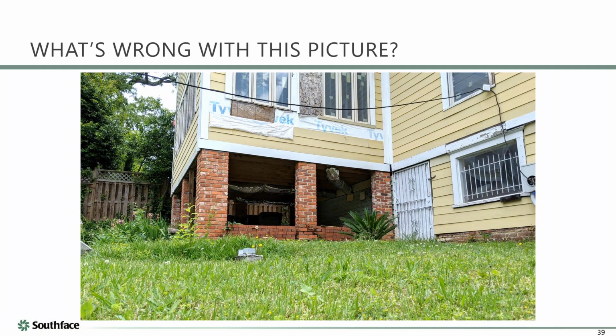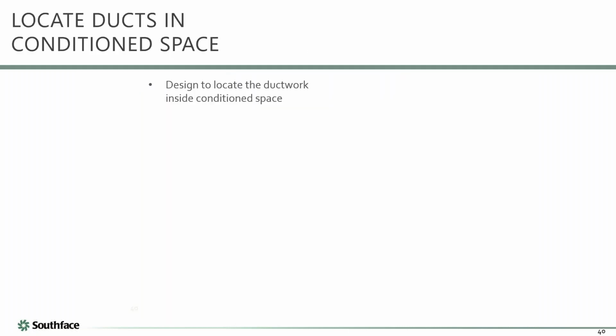Yeah, so we're going to talk about where to put the ducts, and Mike and I both have some strong opinions on that. And anyone can look at this duct system and say, oh wow, that's wrong. We are locating the duct system outside the conditioned envelope in what Mike called an extremely well vented crawl space. But I don't think that putting a duct system in a 130-degree attic is any smarter, to be honest. So we see these things as being obvious, but anytime you put your duct system outside the conditioned space, I think it basically looks like this in my head. Is that more raccoon proof or less raccoon proof than the one in the attic? I'm not sure.